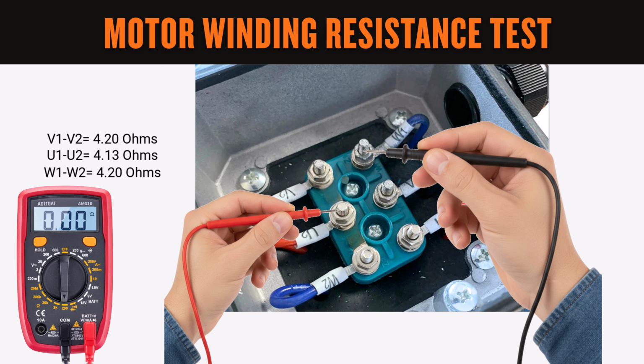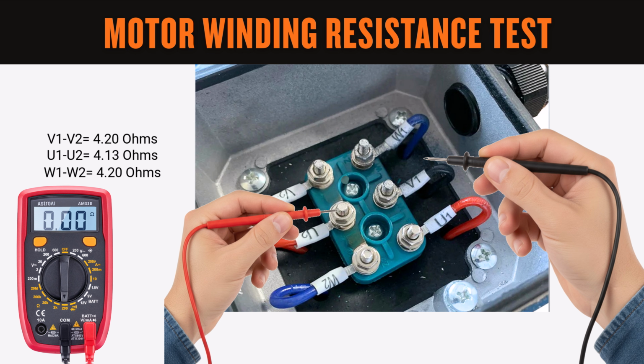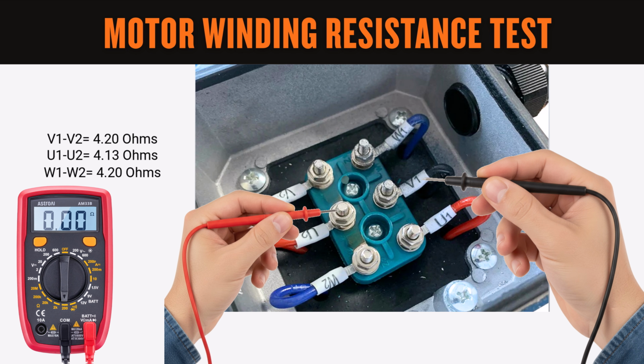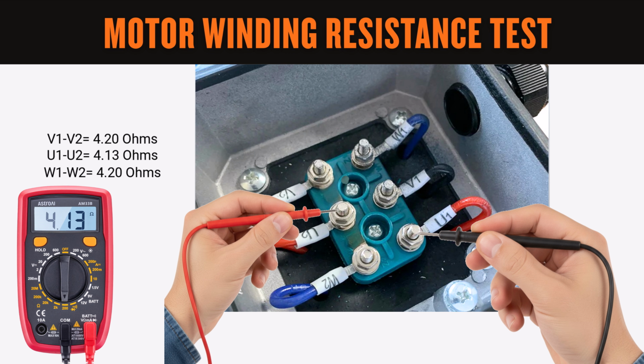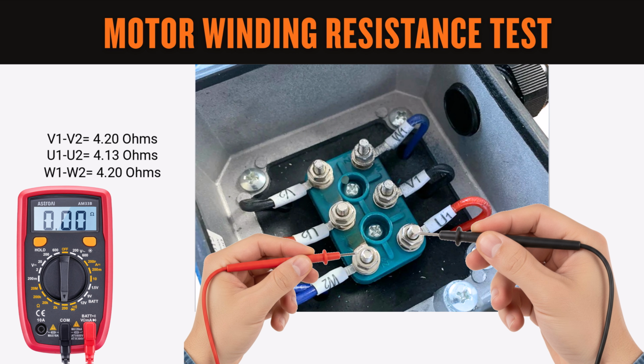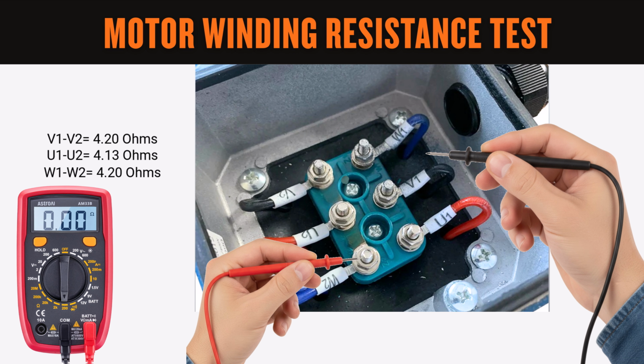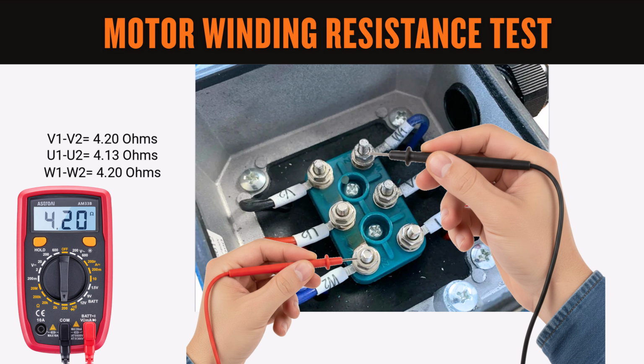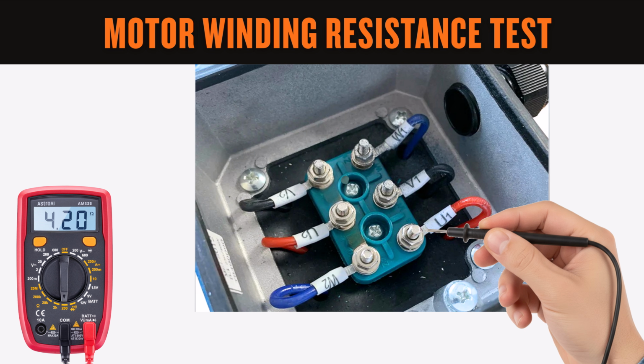Now let's move to the U phase. I'm going to find U1 and U2, again checking where I get continuity so that I can note the resistance value. If the reading is similar, we can say this phase also is okay. And finally, we'll test the W phase, finding W1 and W2 in the same way. Step by step, we confirm continuity and resistance. If everything falls in the same resistance range, that means all 3 phases are in good condition.